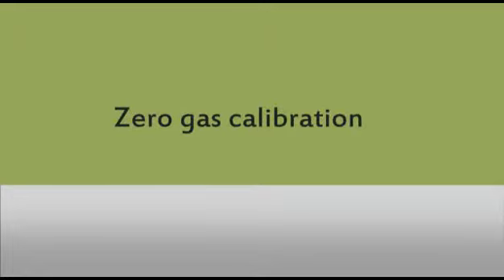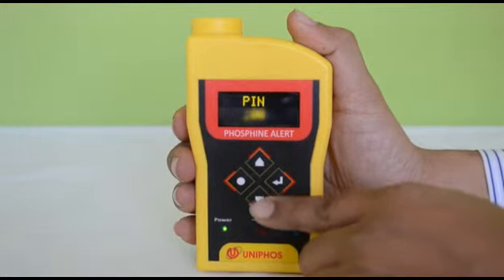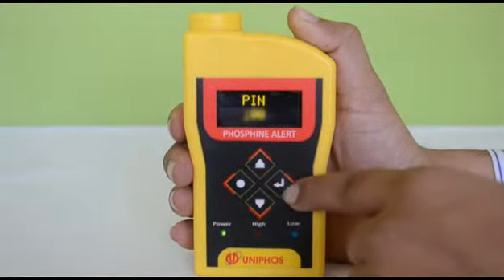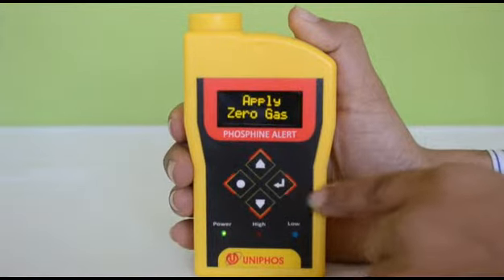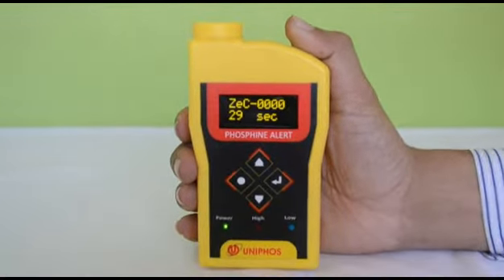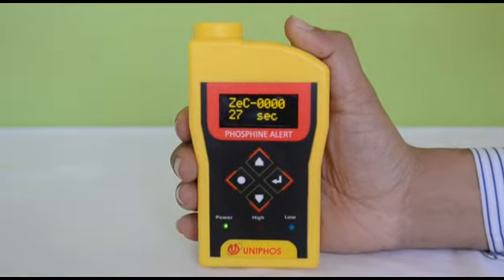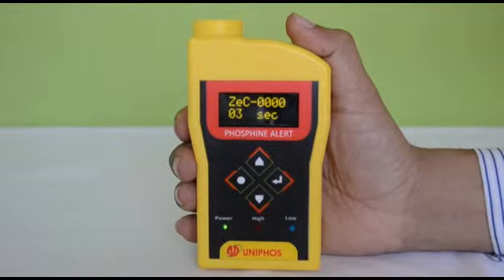Zero gas calibration. Press down key to go into calibration mode and enter password. On successful authentication, instrument will go into zero gas calibration and will sample ambient air for 30 seconds. Zero calibration will be successful only if zero calibration count is in between 0 to 100, else zero calibration will fail. Please ensure that the ambient air is free from the target gas while doing this operation.